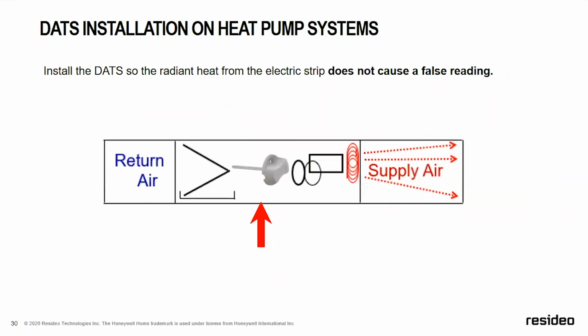This is not typically used in my market, but if you have an air handler with a heat strip, we highly recommend that you put it between the A coil and the blower. Heat strips will cause a lot of false readings from radiant heat, and it will tend to short cycle your system. So this is a very good slide if you're in a market that you use electric heat strips.